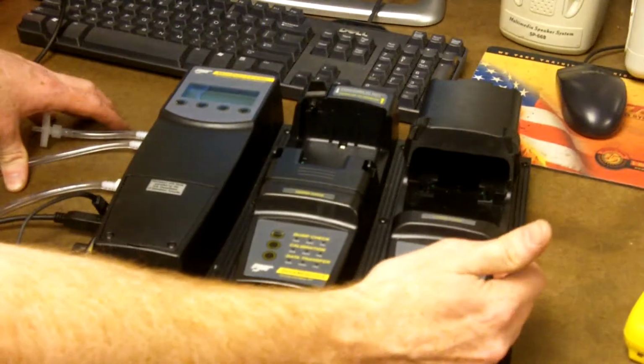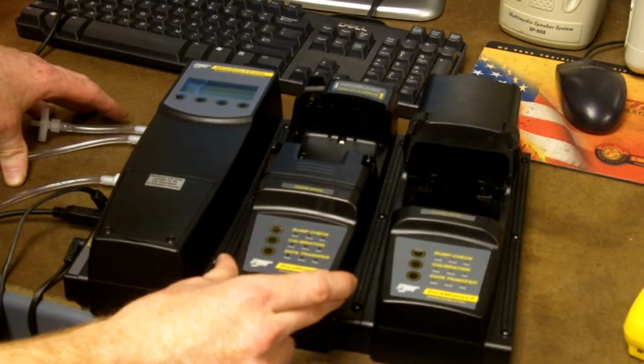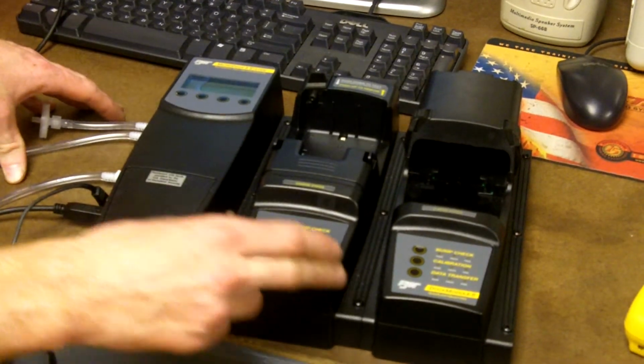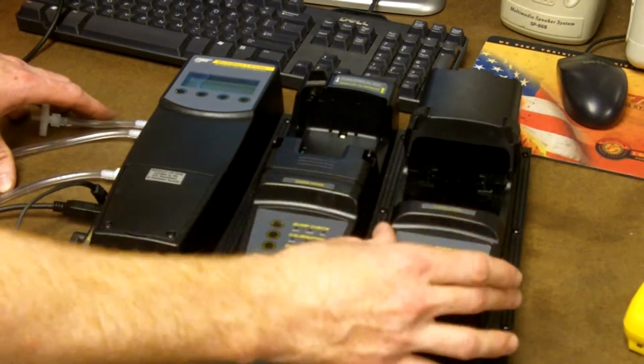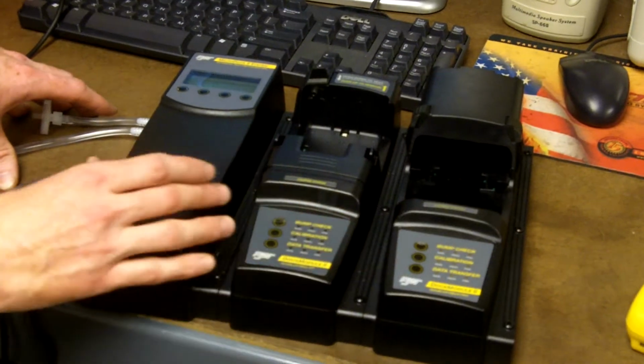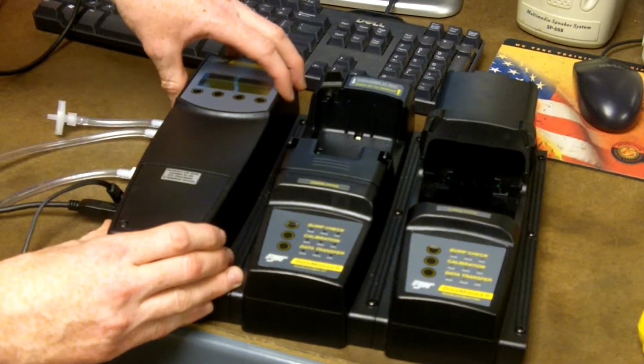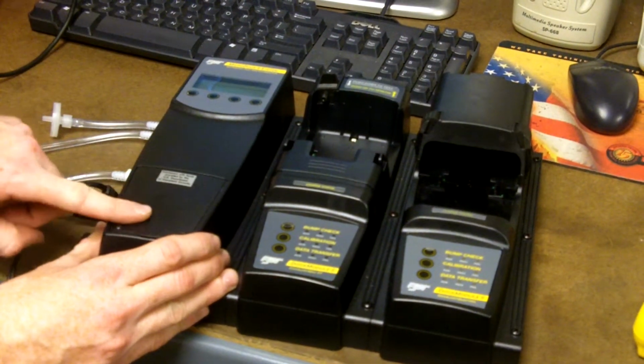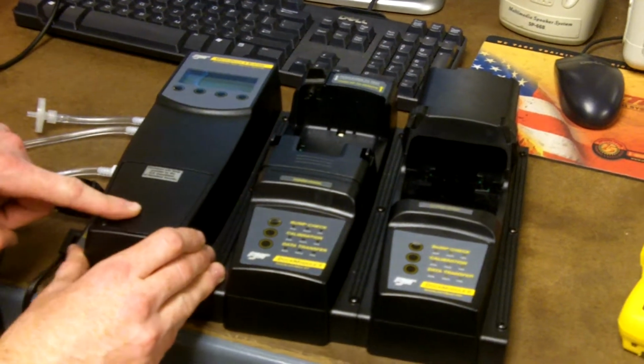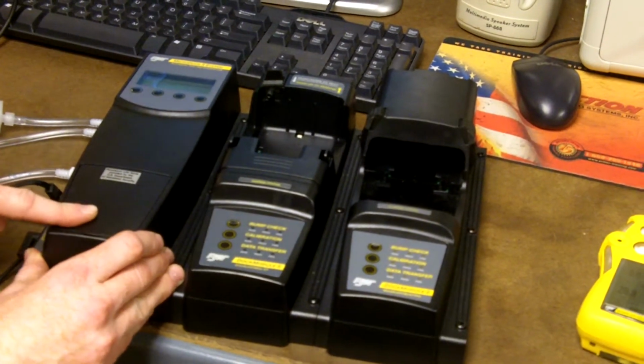So it does, as I said, the Quattro, but it also does the Max XT2. Each slot has its own for each gas detector. And this is the computer portion to it. Batteries could go inside here for battery backup, so it could be in field and actually calibrate and bump test.